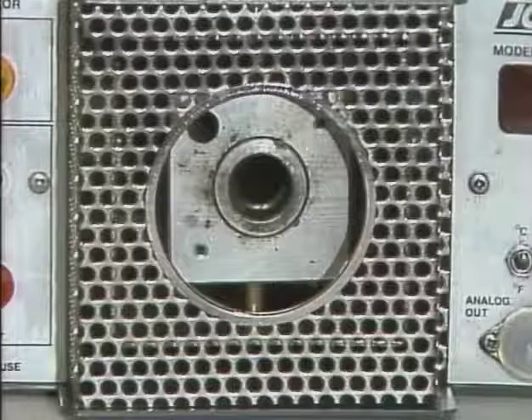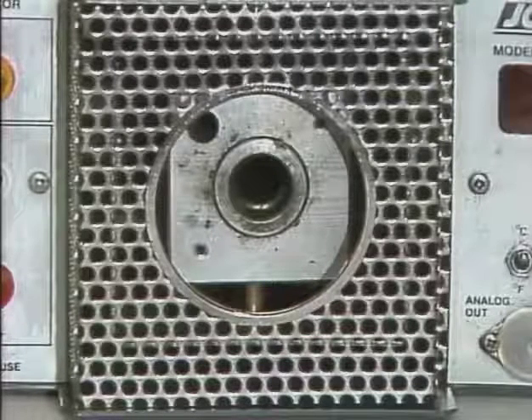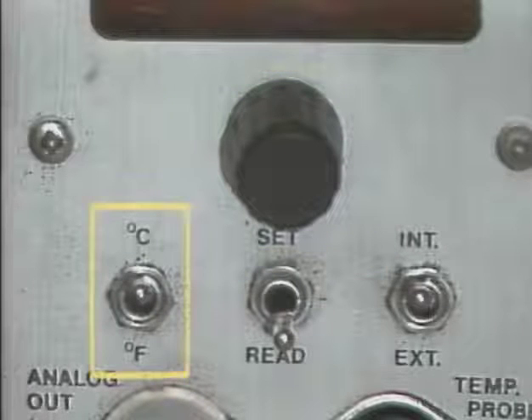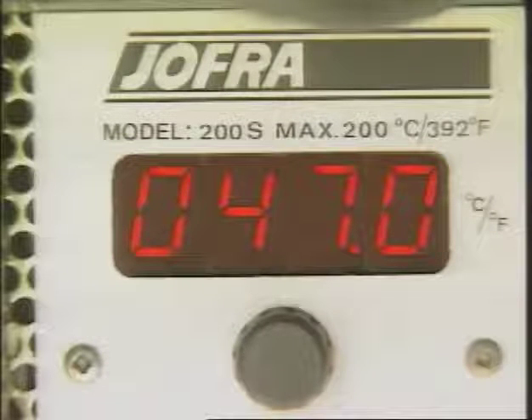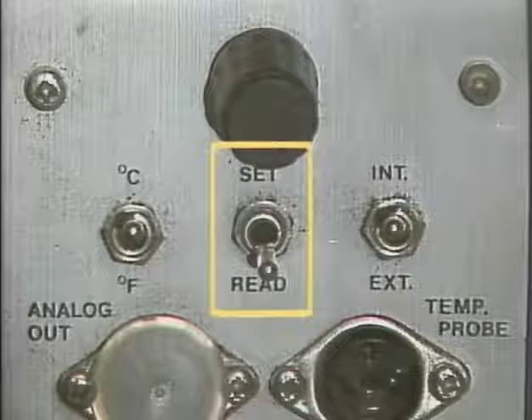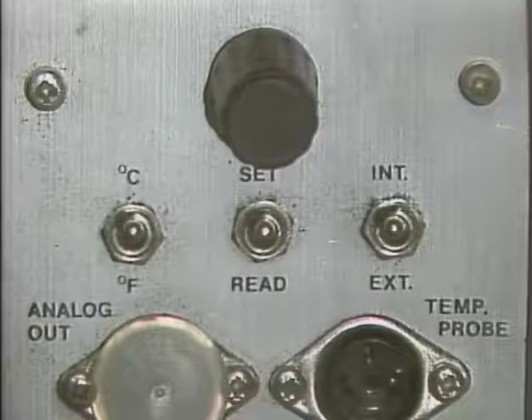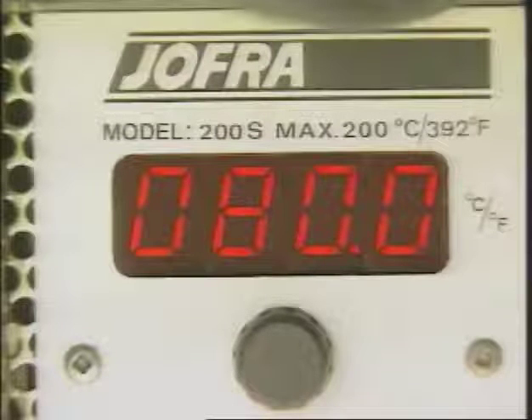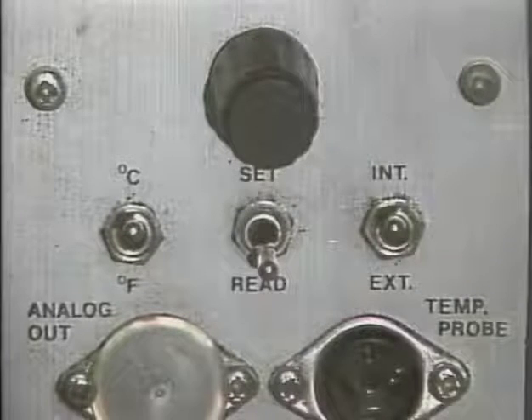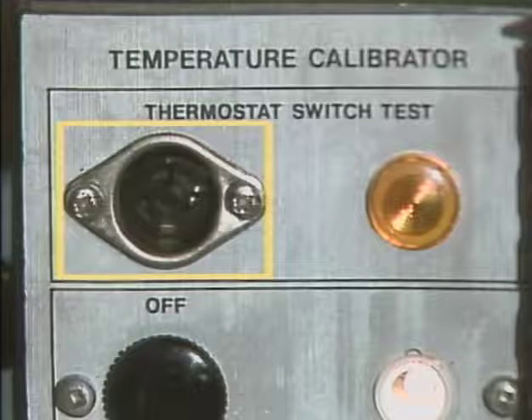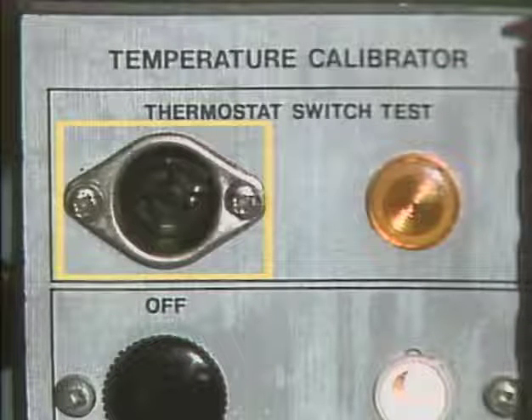As suggested by its name, the heating well provides heat to the insertion tube and to any sensing bulb inserted into the tube. A temperature set knob is used to select the amount of heat to be provided by the heating well. A Celsius/Fahrenheit switch is provided to select whether that temperature is measured in degrees Celsius or in degrees Fahrenheit. A temperature display window shows the selected temperature or the measured temperature at the heating well. A set switch is used to determine whether the temperature that's displayed is the selected or measured temperature. When the set switch is in the set position, the display window shows the temperature that's selected using the temperature set knob. When the set switch is placed in the read position, the display window shows the actual temperature at the heater well.